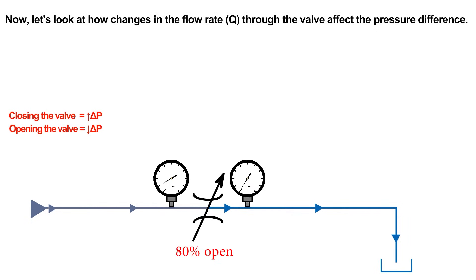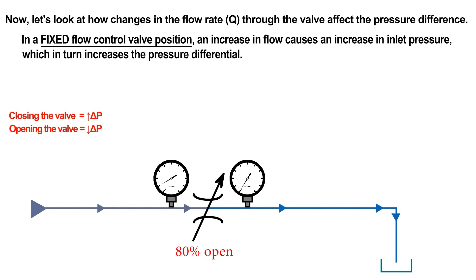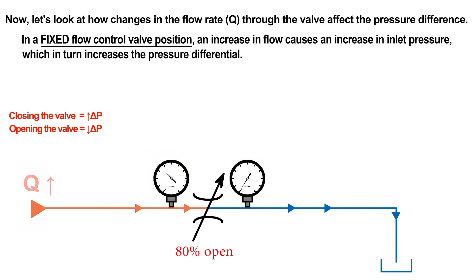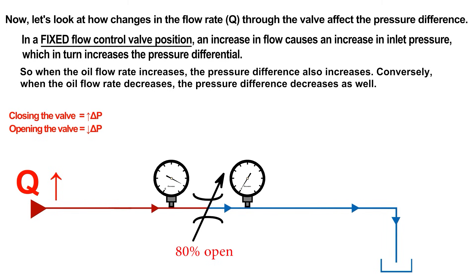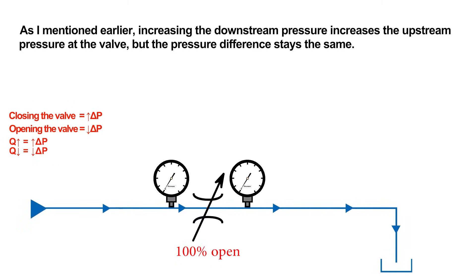Now, let's look at how changes in the flow rate through the valve affect the pressure difference. In a fixed flow control valve position, an increase in flow causes an increase in inlet pressure, which in turn increases the pressure differential. So when the oil flow rate increases, the pressure difference also increases. Conversely, when the oil flow rate decreases, the pressure difference decreases as well. As mentioned earlier, increasing the downstream pressure increases the upstream pressure at the valve, but the pressure difference stays the same.